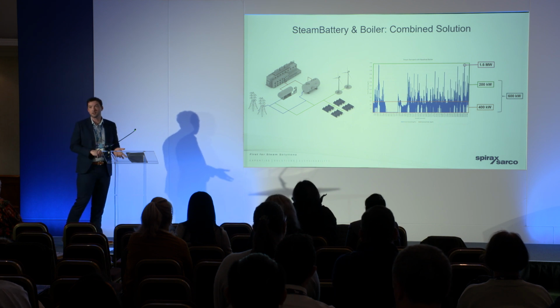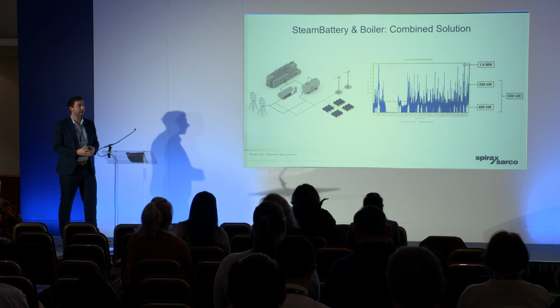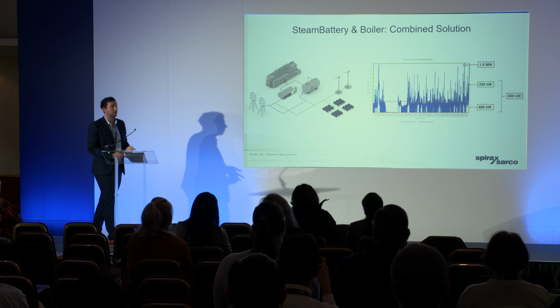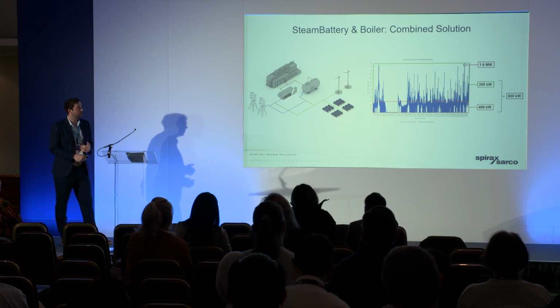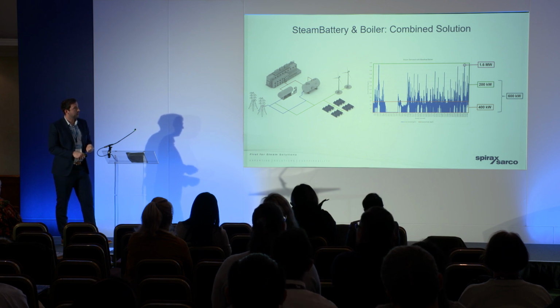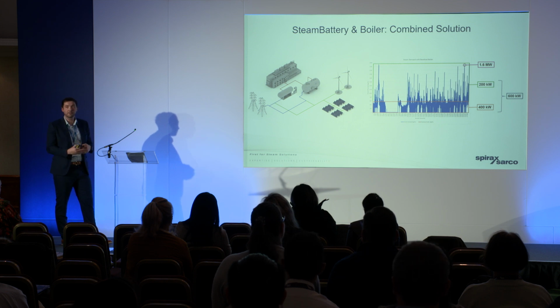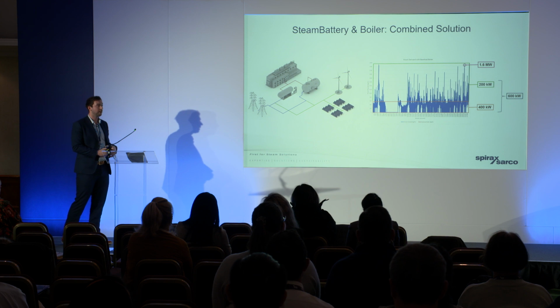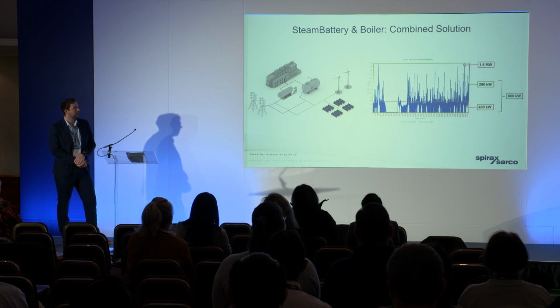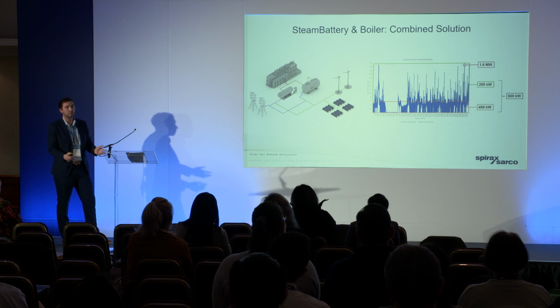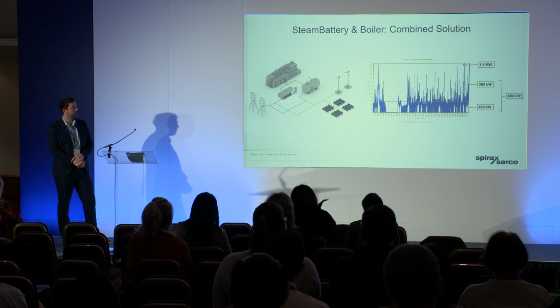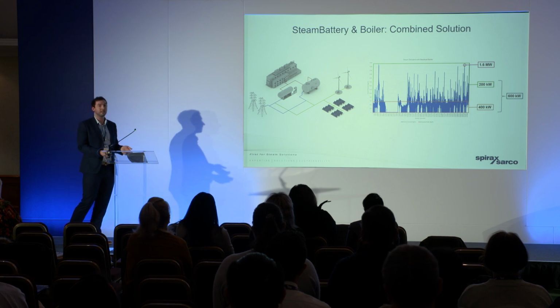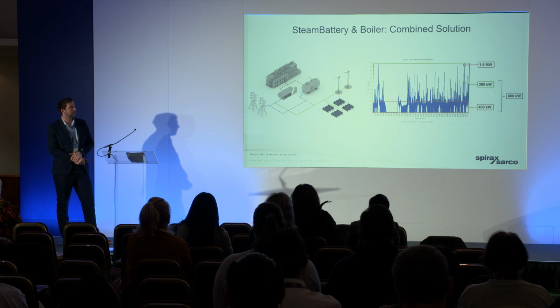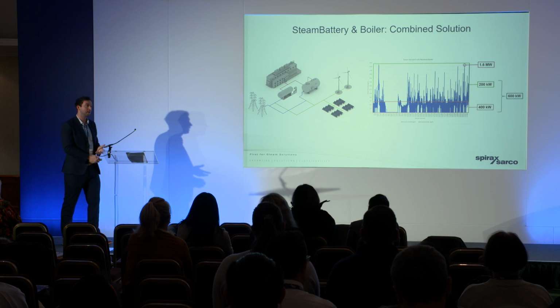And we're starting to see how we can couple our solutions with themselves, so a number of Target Zero solutions together, and even with other technologies like heat pumps and small package boilers, to bring those electrical loads on sites down. So we worked with a customer where this was their steam demand, peaks at 1.6 megawatts equivalent, so a pretty big leap from 400 to 1.6, and 4 times the load when all the sterilizers came on and everything was heating up. A real challenge for them to get that much power into their site. Very restricted, remote, difficult to run more power to their site. What we're able to do is actually split this into 2 sections, a very low-powered small package boiler, and then the steam battery charging over a long period of time and deploying short, sharp peaks into that system. We managed to reduce their electrical requirement from 1.6 megawatts to 600 kilowatts. So a megawatt reduction in the power requirement for that site.